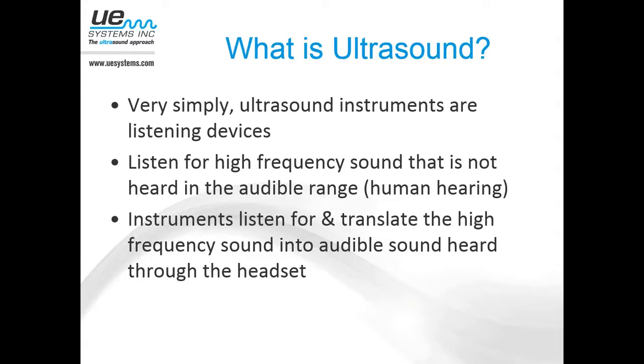We're able to use it in what you may perceive as a very noisy environment in your plant. That noisy environment is noisy to your ears in the low frequency ranges. The high frequency ranges, because of their characteristics, make it usable in those noisy environments for locating the source of leaks, locating bad bearings, locating traps. It's really an interesting technology, and it takes some getting used to. For those of you who currently use the technology, you'll understand what I'm talking about when you're out in the plant. It's amazing what you're able to hear just in those high frequency ranges.